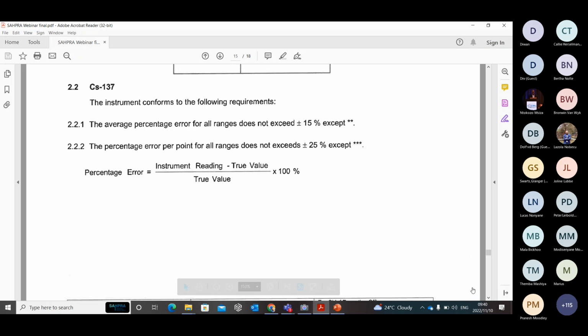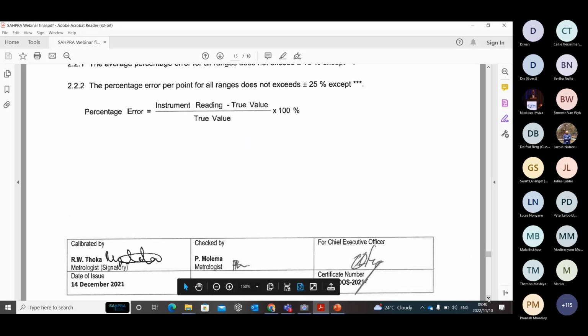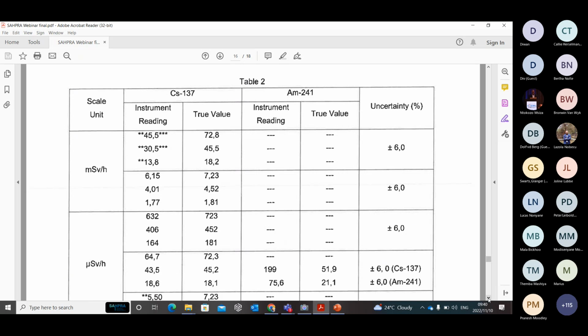And then also, we use the 2 stars, which show that per range, when you combine the 3 points of a range, because we are calibrating per range, where we choose 3 points, at 80% of the maximum value that the instrument can get to, 50% of that, and 20%. In that range, when you see the 2 stars on your certificate, it means that the average of all the points differs from the true value by more than 15%. Hence, you will see those double stars.